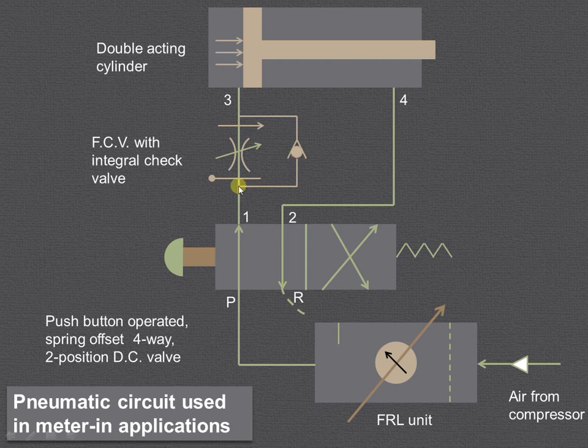Therefore it must pass through this particular restricted opening, and therefore a controlled rate of air is achieved. This air coming inside the cylinder at a controlled rate causes the forward motion of the piston and piston rod to be slow.